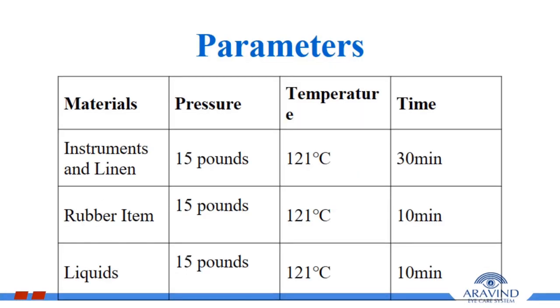Parameters: instruments and linen, 15 pounds, 121 degrees Celsius, 30 minutes. Rubber items, 15 pounds, 121 degrees Celsius, 10 minutes. Liquids, 15 pounds, 121 degrees Celsius, 10 minutes. High speed autoclave in between sterilization, temperature 134 degrees Celsius for 7 minutes.